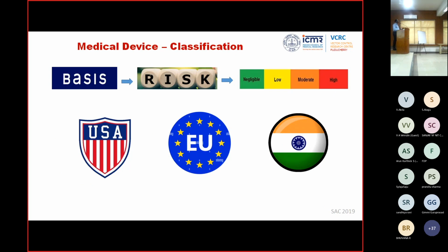Even knowing all these things, the very basis of classifying medical devices is only one factor: the risk to the consumer, that is the patient, or the one who is using the medical device. That is the only criterion we use for classification of medical devices. We have three sets of categorization: the US classification, the European classification, and of course the Indian classification.